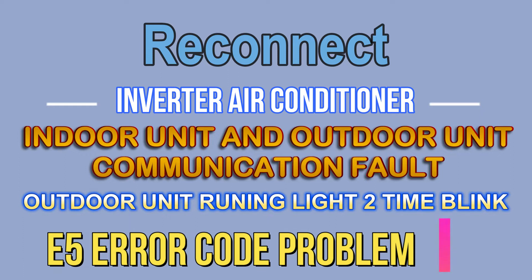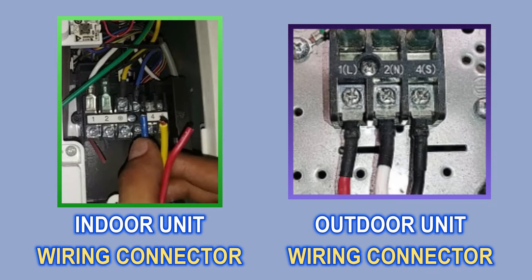This error can occur in your AC due to four reasons. The first reason may be the supply wire going to your indoor unit and outdoor unit. You should look at the connector of the indoor unit and the connector of the outdoor unit — there should be the same color code. If the same color code wire is not installed in the connectors of the indoor unit and the outdoor unit, then you will get this error.